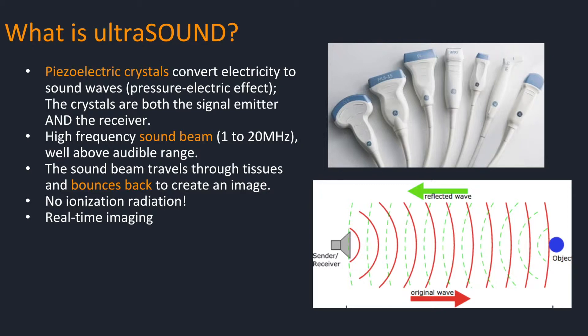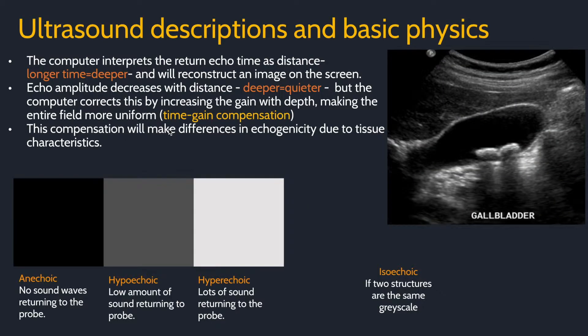This modality is non-ionizing and real-time. To make an image, the computer makes a few assumptions. First, it assumes that the longer the return echo time, the deeper the echo was — longer time means deeper. It also assumes that echo amplitude, or loudness, will decrease as the echoes are further away. However, we want to look at a uniform field, so the computer will correct for this by increasing image gain with depth, making a more uniform field.